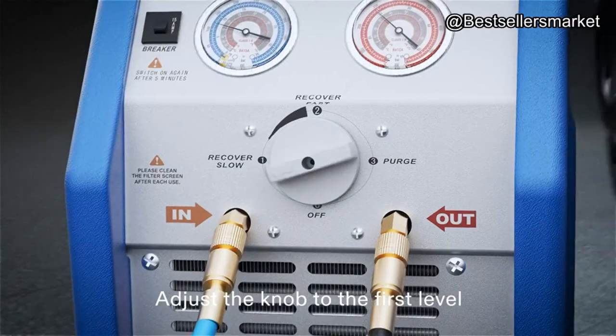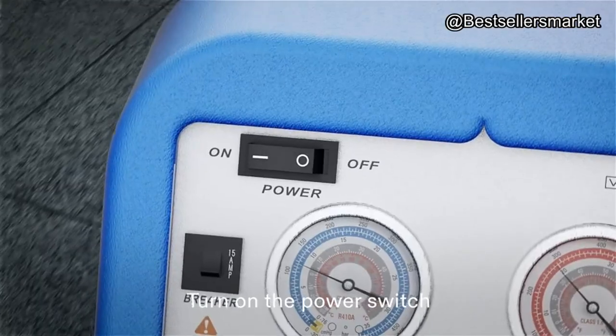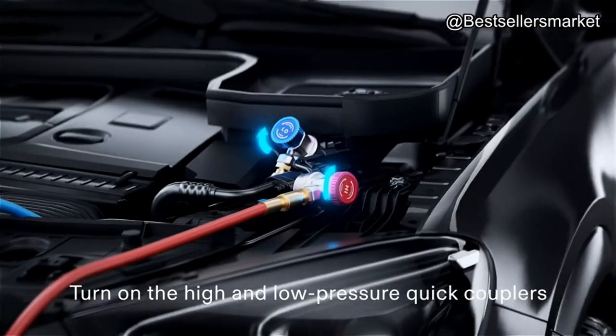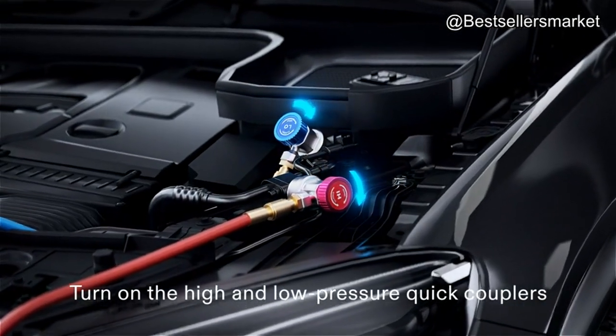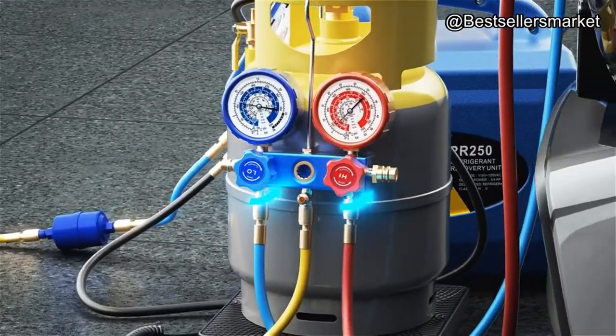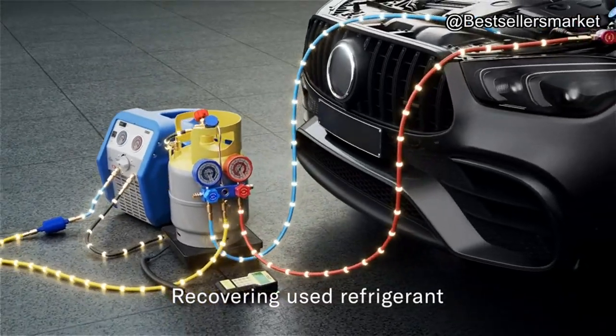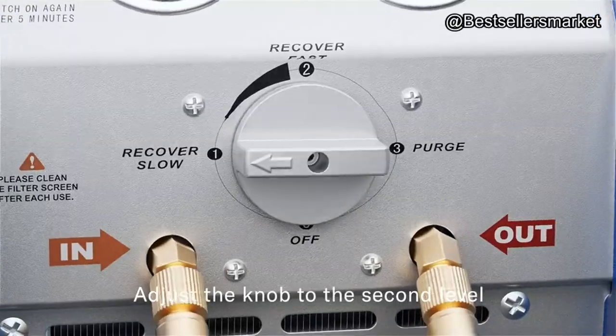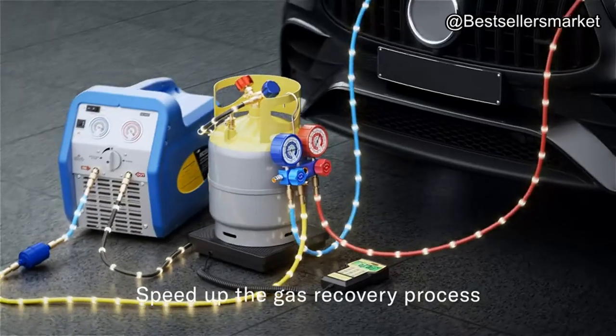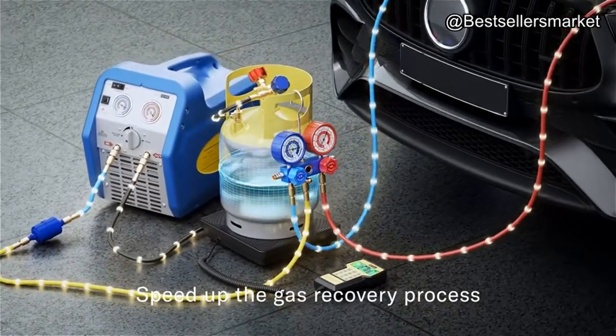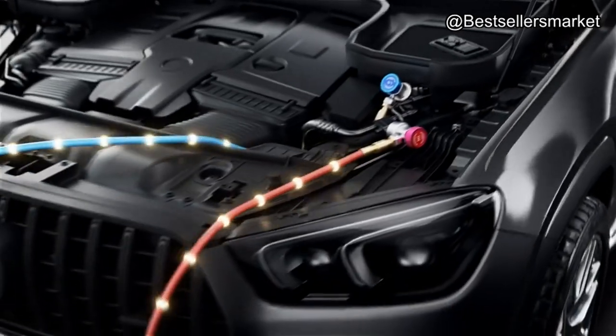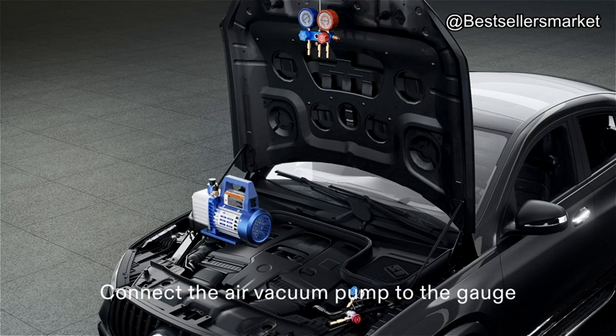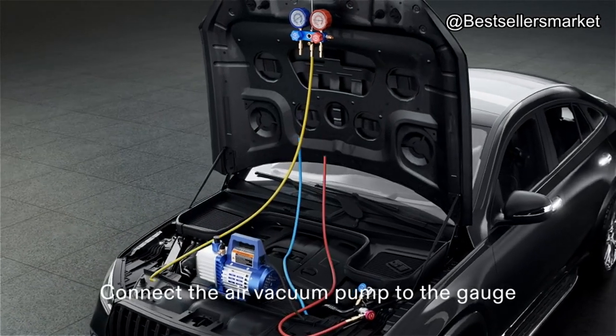Large viewing glasses on the manifolds allow for easy monitoring of refrigerant flow, while high-quality, colorful pressure gauges provide clear and accurate readings. The color-coded hoses are a game-changer. They help you easily identify the high-pressure side, red, low-pressure side, blue, and the filling hose, yellow. Made of flexible, durable rubber with a leak-proof seal design, these hoses are built to last and withstand rigorous use.